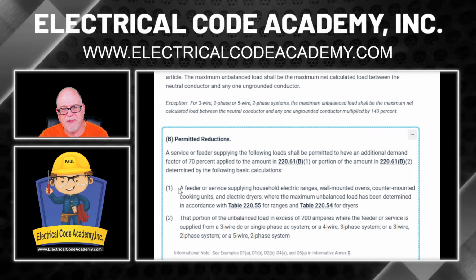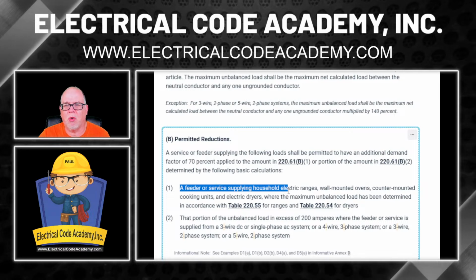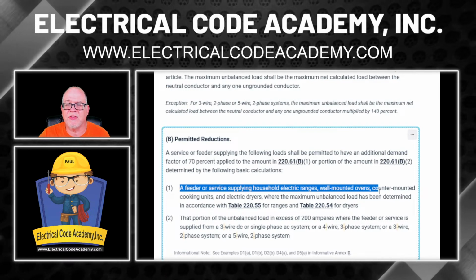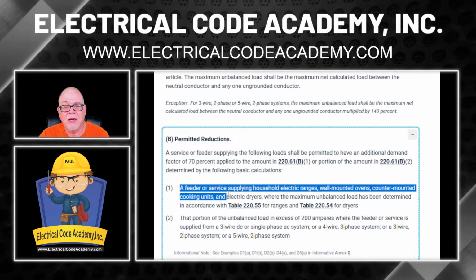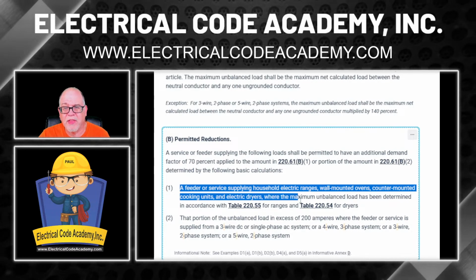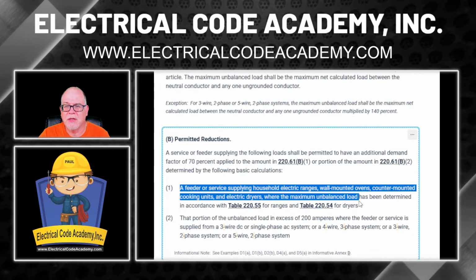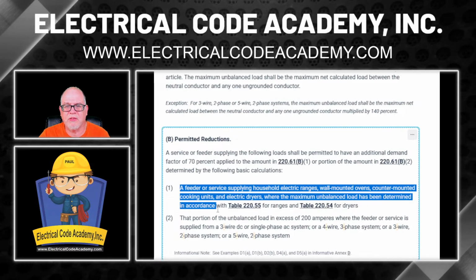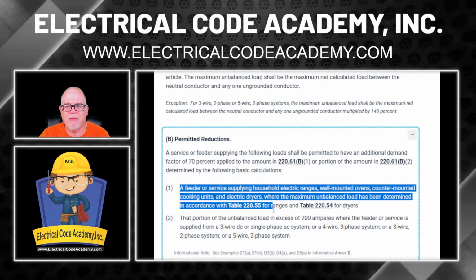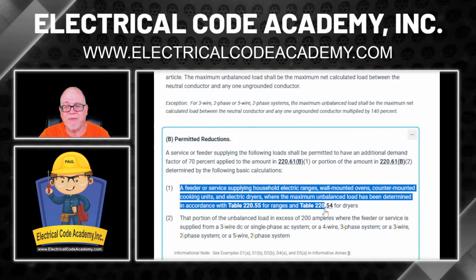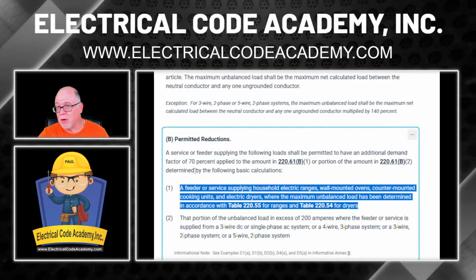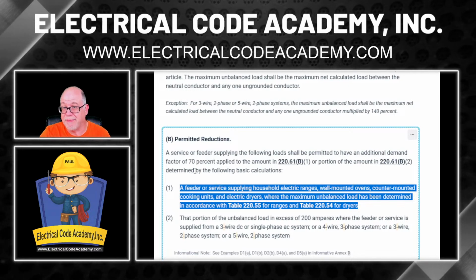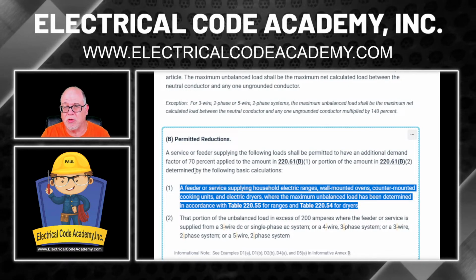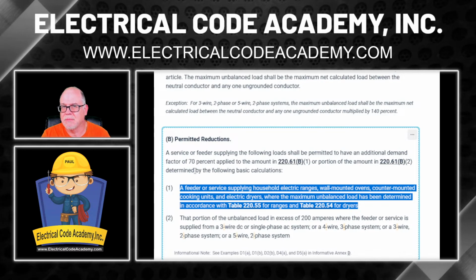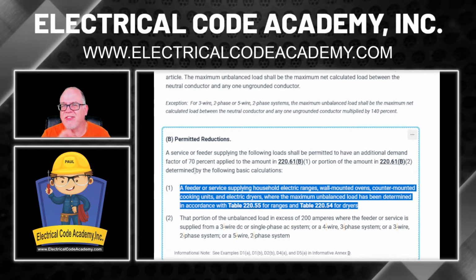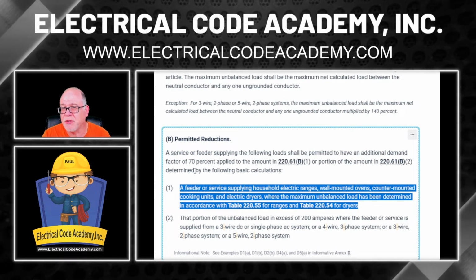So it says a feeder or service supplying household electric ranges, wall-mounted ovens, counter-mounted cooking units, and electric dryers where the maximum unbalanced load has been determined in accordance with Table 220.55 for ranges and Table 220.54 for dryers. Well, we only had one, so that was 5,400. That is our value that we use. So I can take that and I get to apply a 70% additional demand to that.